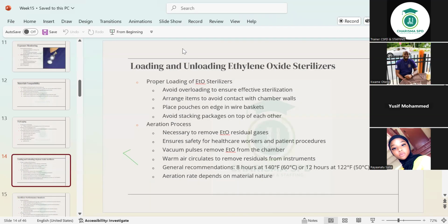The general recommendation for the aeration process is 8 hours at 140 degrees Fahrenheit. You see that is not cold, right? Even when we're walking outside and the outside temperature is 100 degrees in the summertime, how do we feel? Hot. Very, very hot, right?